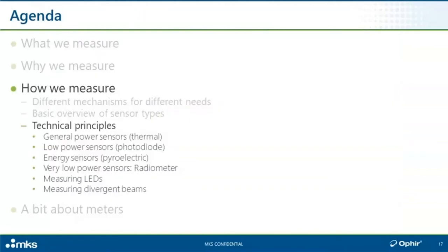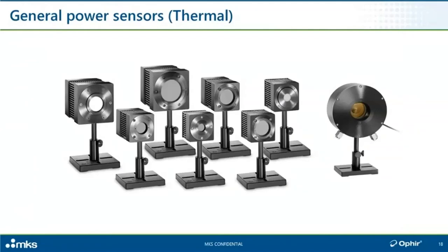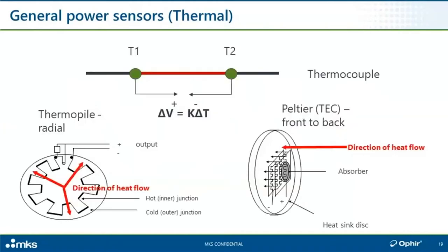Now let's drop down to a lower altitude and get into the more detailed technical principles. Let's begin with general power sensors for moderate to high power levels — from a couple of tens of microwatts up to 120 kilowatts in our case. You may be wondering why one would use such an indirect mechanism as heat absorption. It has its pluses and minuses — one of the first words you learn in any engineering curriculum is trade-off. Basically, dissimilar metals — bimetallic: metal A, metal B, metal A — suitably chosen and connected — have a physical principle that says if there is a temperature difference between two points, there's going to be a voltage difference between them as well.